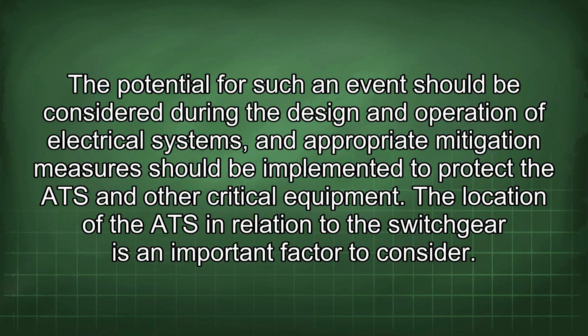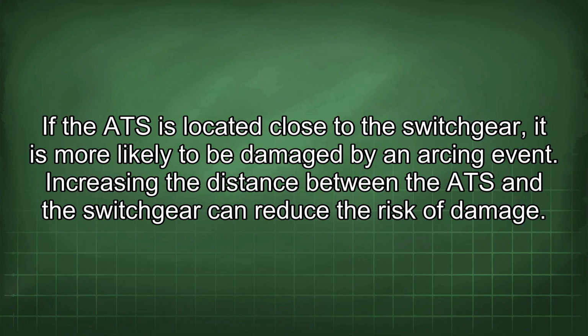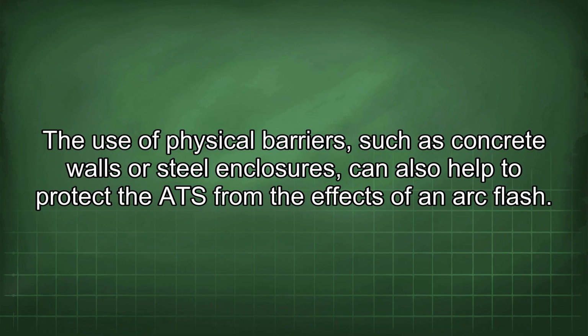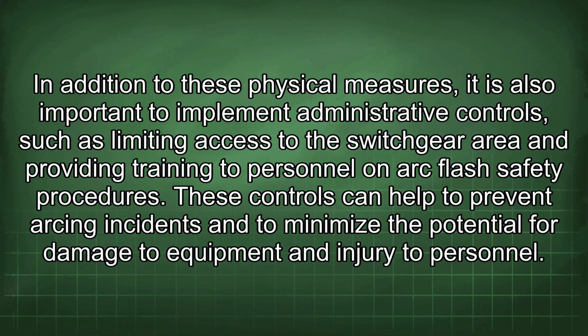The location of the ATS in relation to the switchgear is an important factor to consider. If the ATS is located close to the switchgear, it is more likely to be damaged by an arcing event. Increasing the distance between the ATS and the switchgear can reduce the risk of damage. The use of physical barriers, such as concrete walls or steel enclosures, can also help to protect the ATS from the effects of an arc flash. In addition to these physical measures, it is also important to implement administrative controls, such as limiting access to the switchgear area and providing training to personnel on arc flash safety procedures.